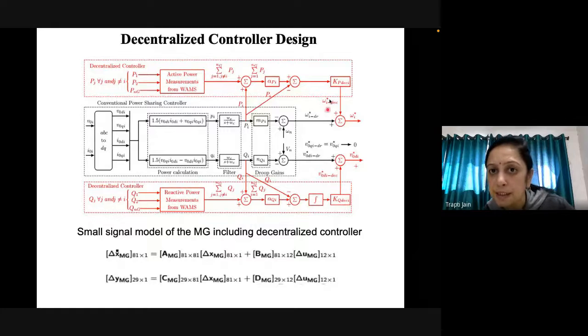Now you can see the difference: here we do not have any integral term, because the real power droop control is very accurate for these microgrids, but the reactive power droop control is not that accurate. So to reduce the error, we have incorporated an integral term here.